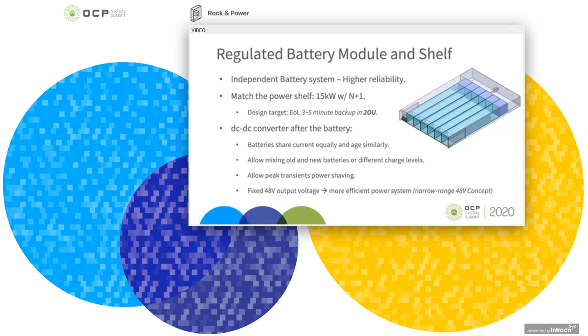Our design is basically going to be a regulated battery system with a DC to DC converter after the battery, which gives several benefits. First, batteries share current equally and age similarly. It also allows mixing old and new batteries with different charge levels on the same rack. On the side, it also helps with transient peak power shaving. The other benefit of having the fixed 48 volt output voltage is that it gives a more efficient power system with a narrow range 48 volt concept that I will explain later.